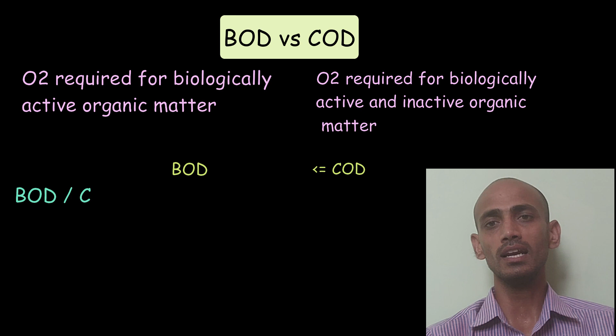The BOD to COD ratio indicates the biodegradability of the wastewater. The higher the BOD to COD ratio, the higher the biodegradability, so we can go for biological treatment. BOD ultimate to COD ratio should be between 0.92 and 1. However, BOD5 to COD ratio should be between 0.63 and 0.68. If the ratio is very low, then we cannot give biological treatment, and we have to go for chemical treatment.